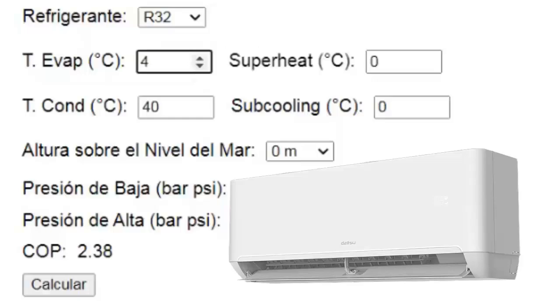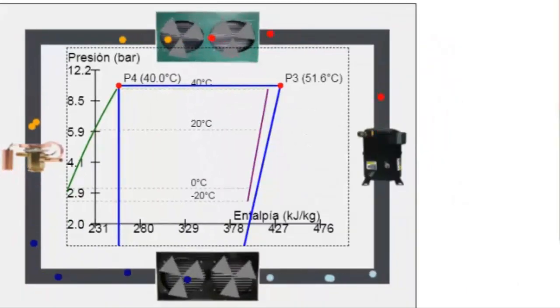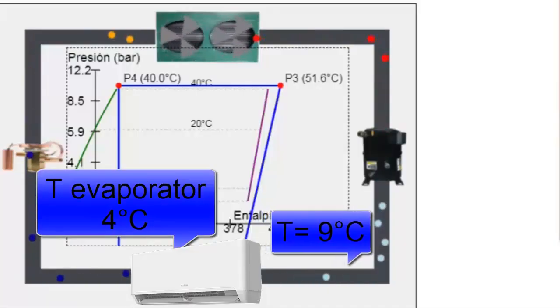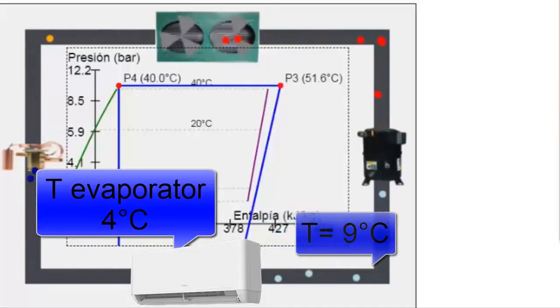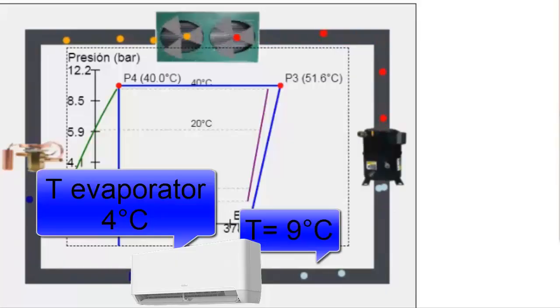For a more precise calculation, we will set the superheat adjustment to 5 degrees Celsius at the evaporator outlet. Let's remember that superheat is the increase in temperature of the refrigerant gas inside the evaporator coil, located in the indoor unit.